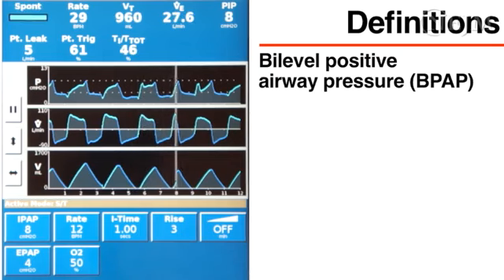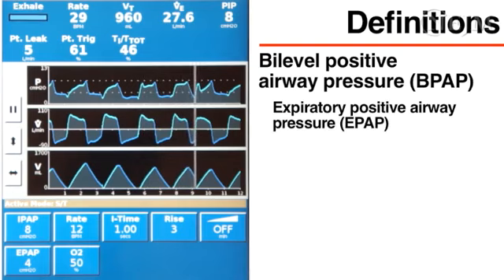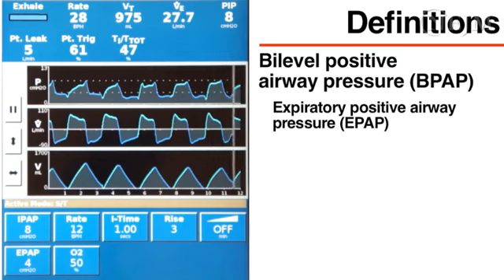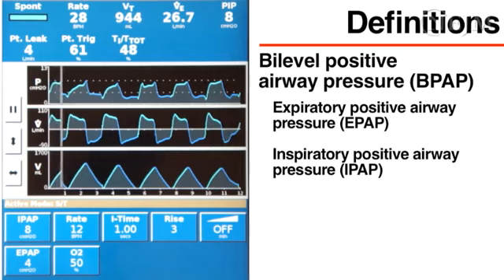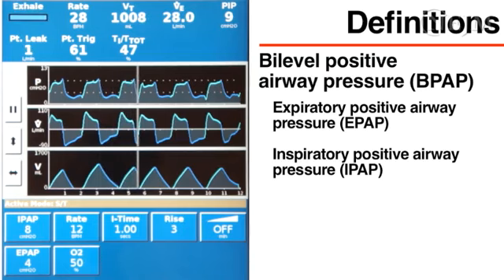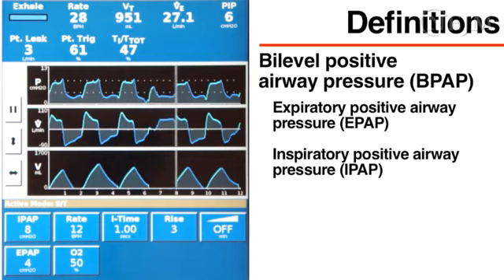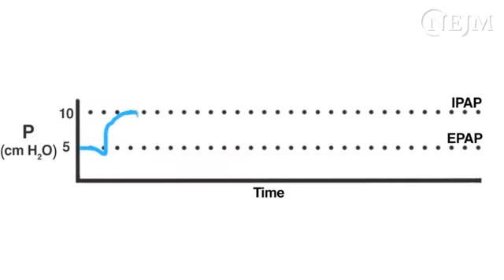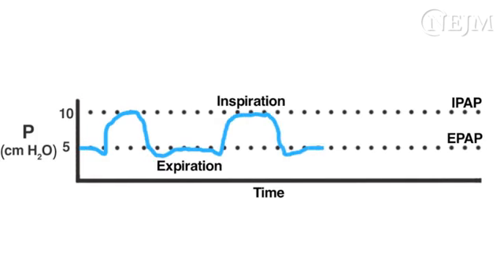In BPAP, the ventilator cycles between two pressures, delivering an expiratory positive airway pressure, or EPAP, during expiration, and a higher inspiratory positive airway pressure, or IPAP, during inspiration. The difference between EPAP and IPAP provides pressure support to the patient, thereby increasing tidal volume and directly supporting ventilation. This graph shows airway pressures in a patient receiving BPAP. The tidal volume correlates with the difference between the expiratory and inspiratory pressures.